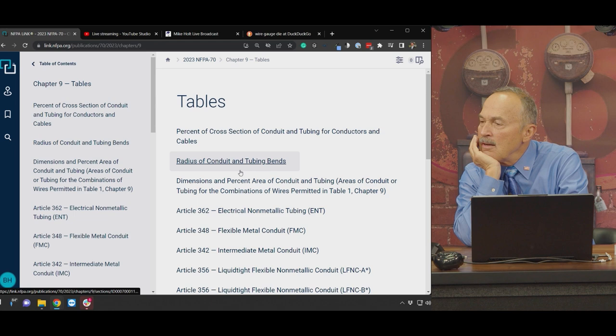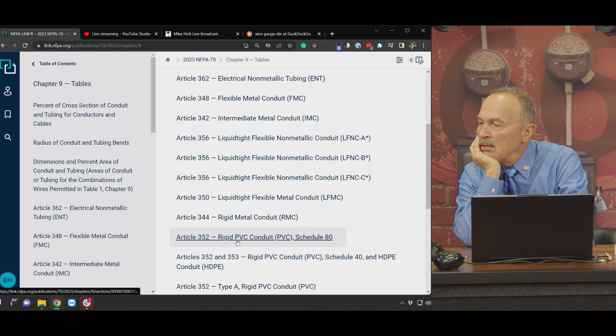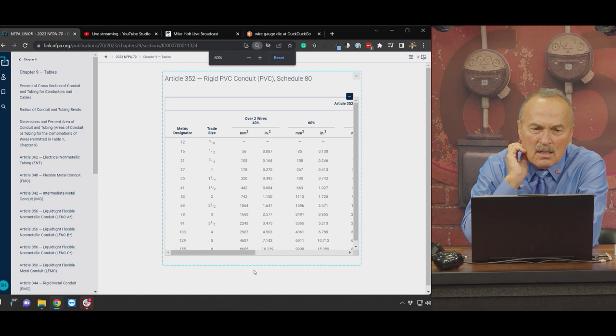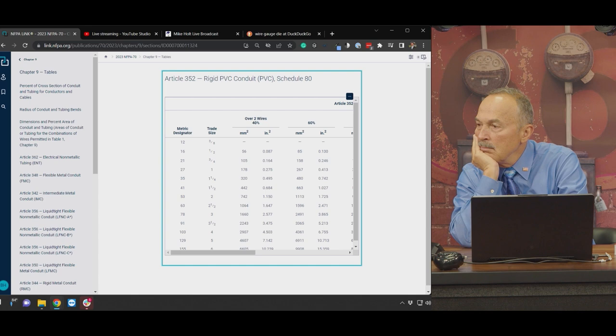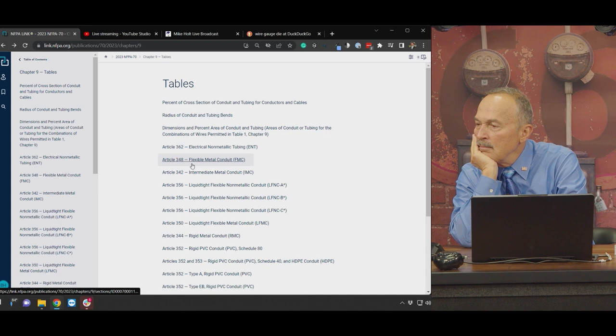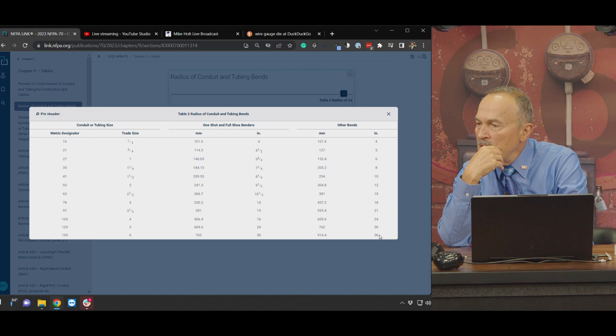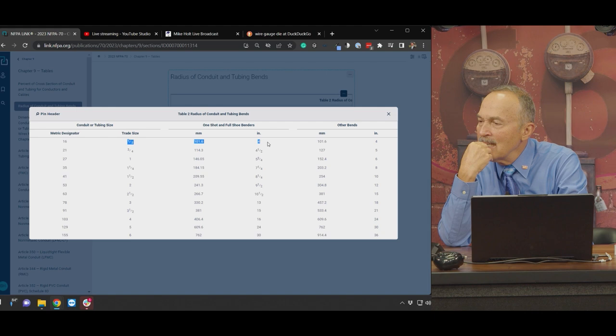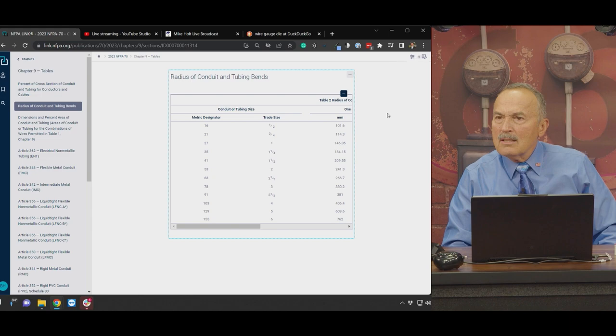Let's click on Table 2, Chapter 9 to see what the radius is. Looks like some three-quarters and half inch conduit. If it's a half inch, the radius is four inches. So a plumbing 90 is definitely not going to work. That was 352.24A. Just write them all up so they know you're really smart.